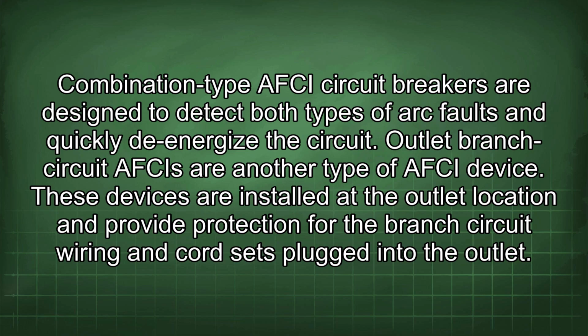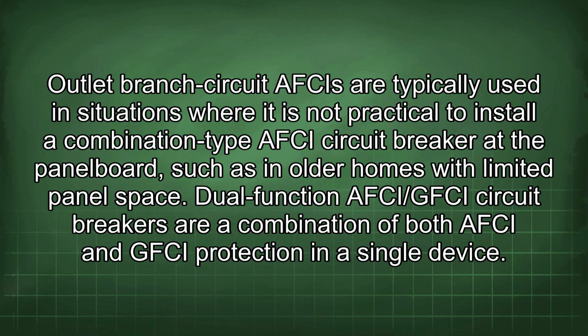Outlet branch circuit AFCIs are another type of AFCI device. These devices are installed at the outlet location and provide protection for the branch circuit wiring and cord sets plugged into the outlet. Outlet branch circuit AFCIs are typically used in situations where it is not practical to install a combination type AFCI circuit breaker at the panel board, such as in older homes with limited panel space.